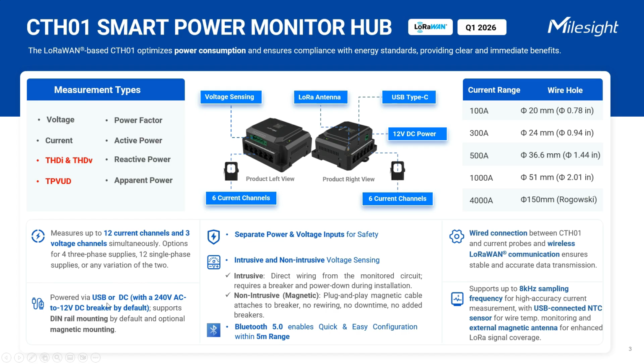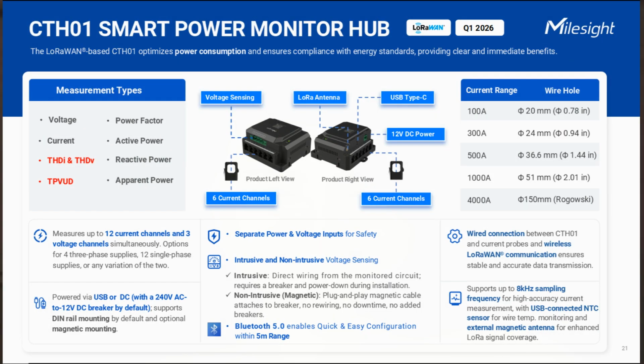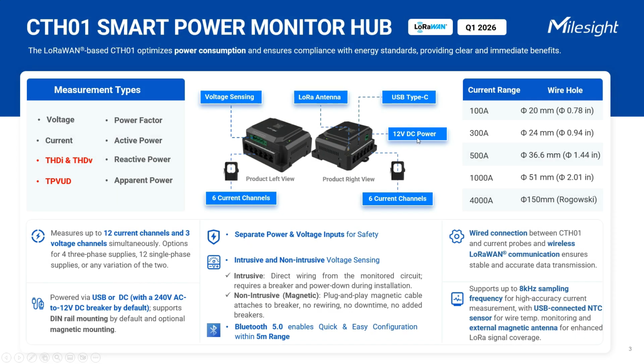It's powered through a dedicated DC or USB port, and it comes with a breaker by default that converts 240 volts AC to 12 volts DC safely. When it comes to voltage sensing, that's handled through a separate voltage input port, and this port is designed to accept AC input only, with support for both intrusive and non-intrusive sensing methods, giving installers flexibility depending on their site conditions. For the intrusive method, a wire is tapped from the measured circuit and connected to the voltage input port. This setup requires powering down the system during installation, and typically needs an extra breaker added, so it's more suitable for new projects or when rewiring is already part of the plan.